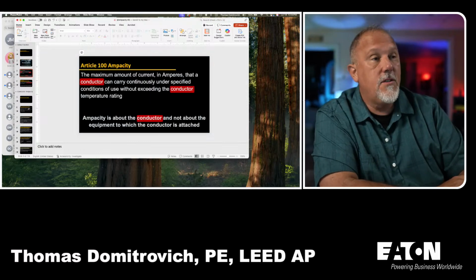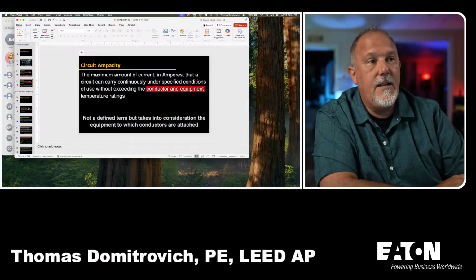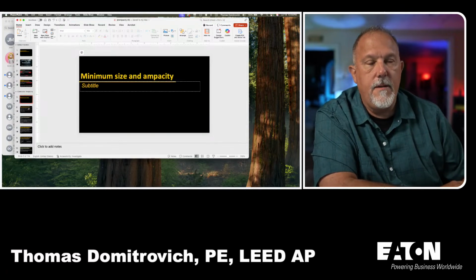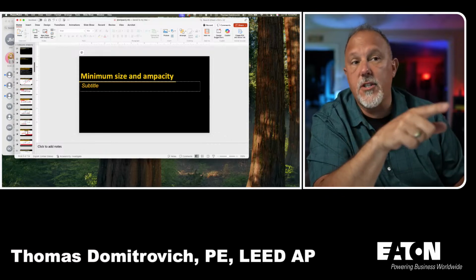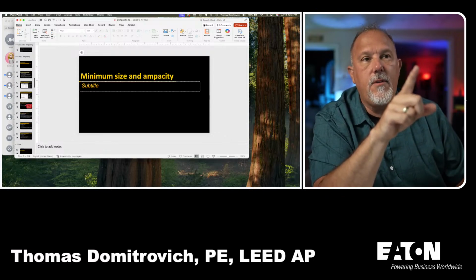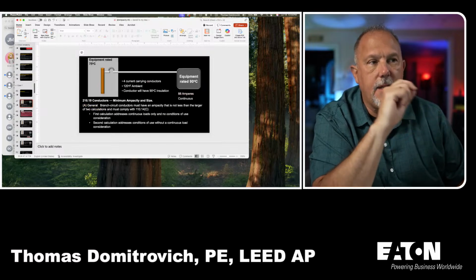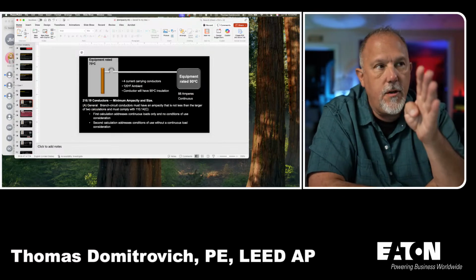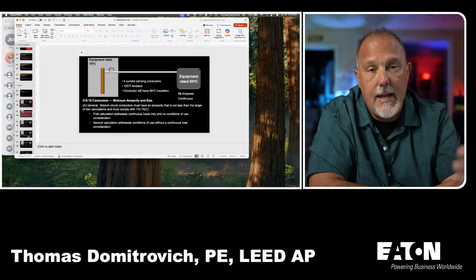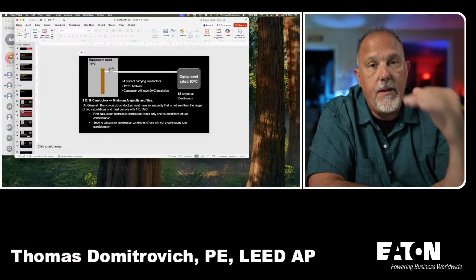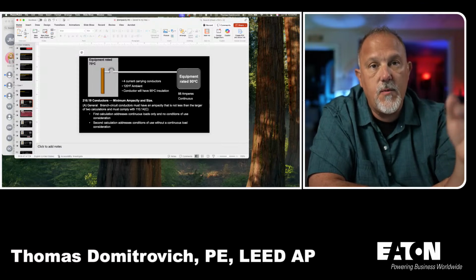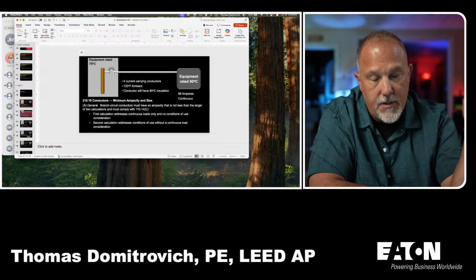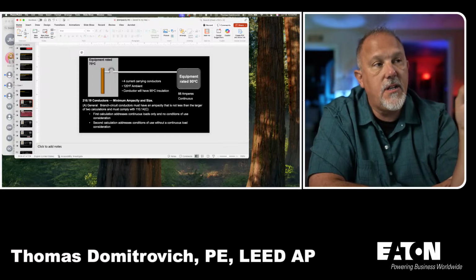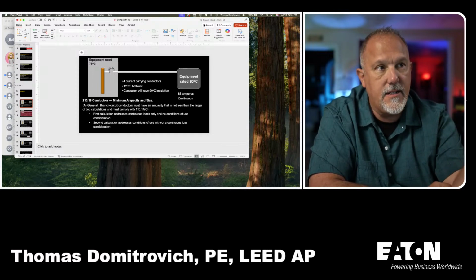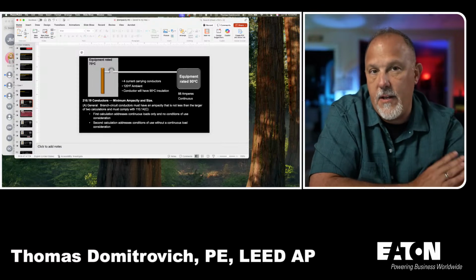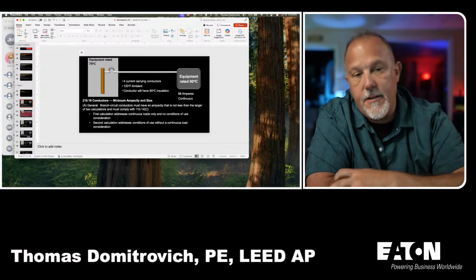So here's what we got. We went over conductor ampacity. We went through all the discussions of minimum size. We talked about the circuit ampacity. And we went through case one. Remember, case one was 4 current carrying conductors at 120 degrees, so a hot ambient. We're into the multiple conductors in a raceway factor that we have to apply. And then we know the conductors have a 90 degrees C insulation, and one end of the conductor was terminating at 90, the other end at 75.